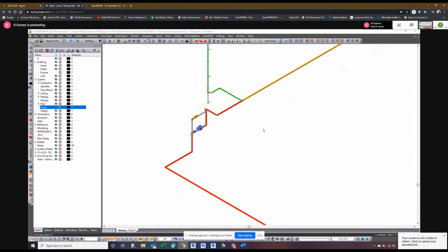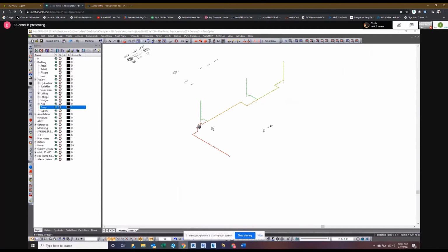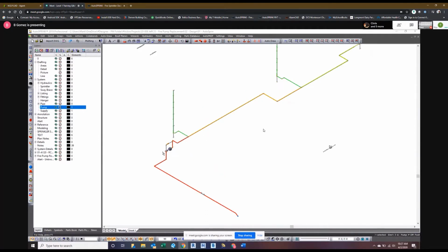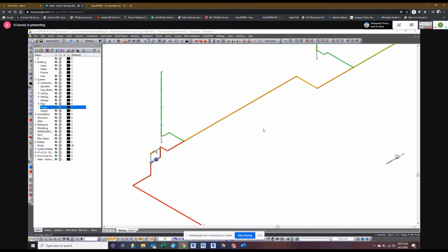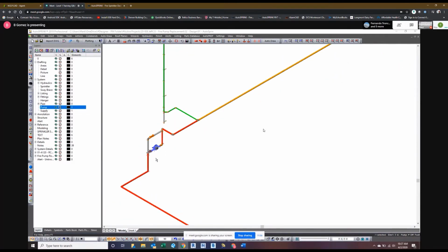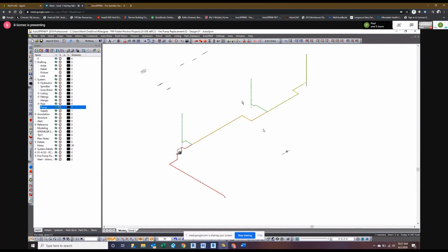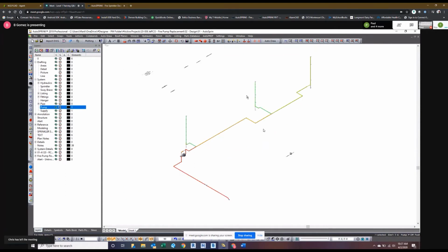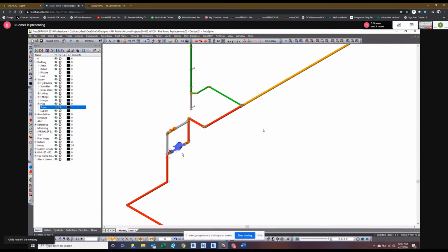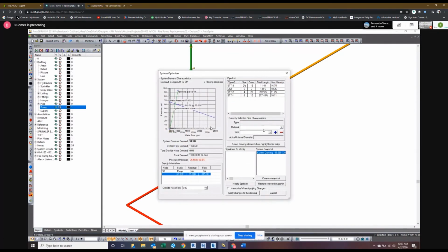All right. You see that? Yes, sir. Cool. So one kind of problem that I was having, Brian: normally when I do the standpipe calculation, I'll do the flow of the manual devices. And when I do flow, you can see here, I have three stairwells flowing 500 at the most remote, 250 in between. So I'm trying to flow the 1,000. When I calculate flowing devices, it's calculating 1100 GPM, so it's adding 100 somewhere.